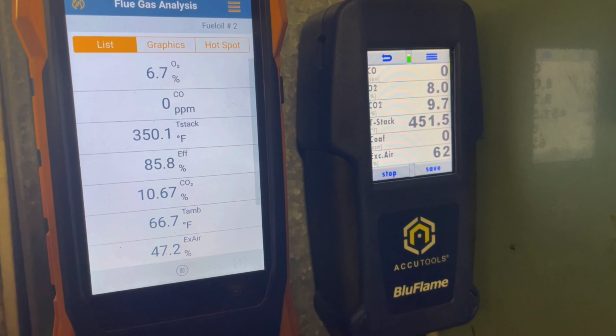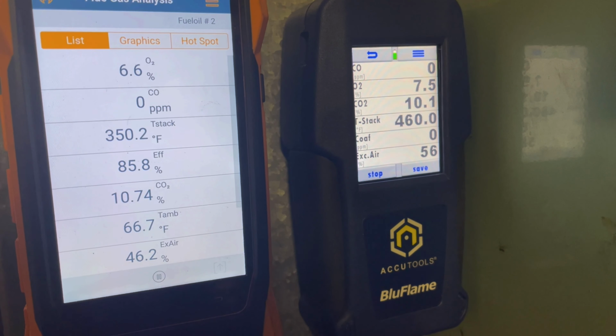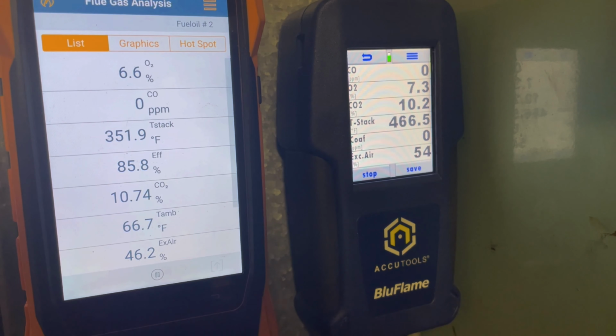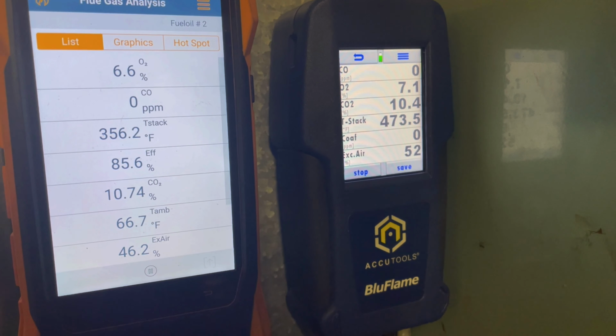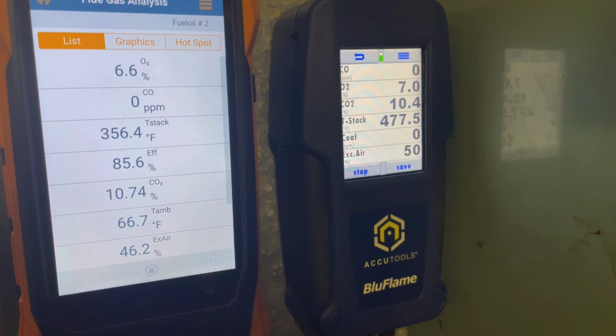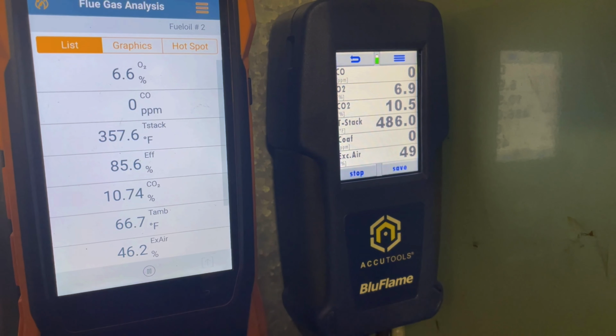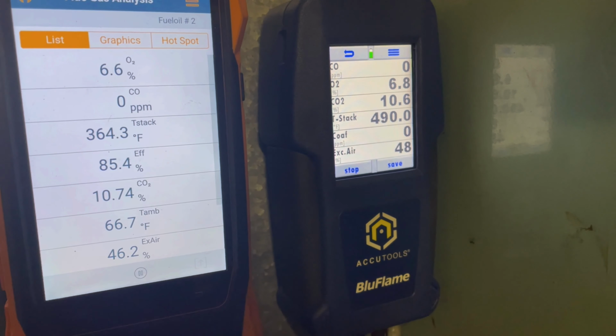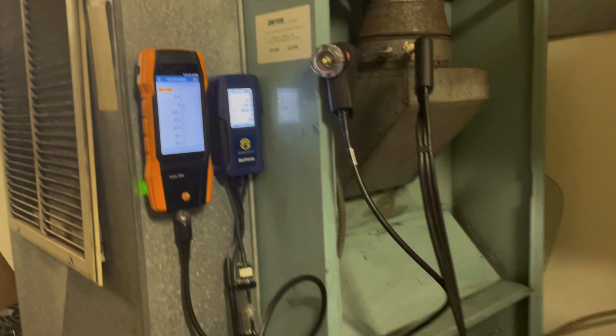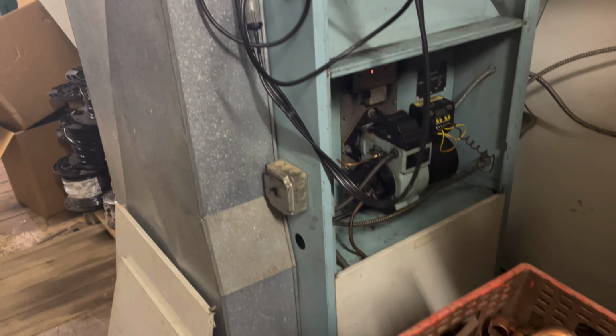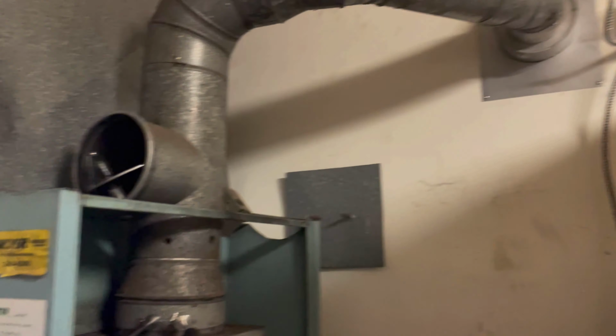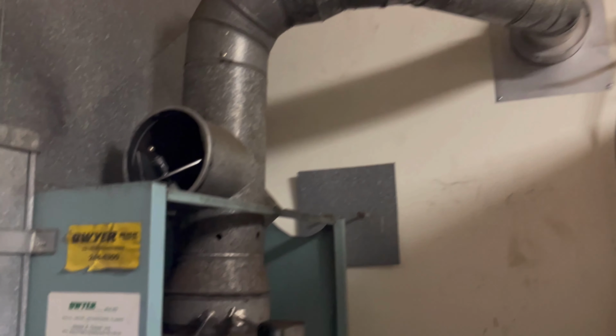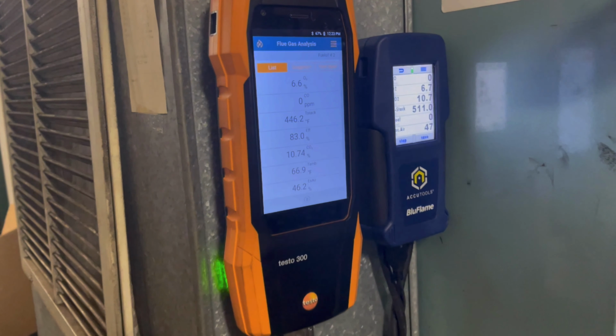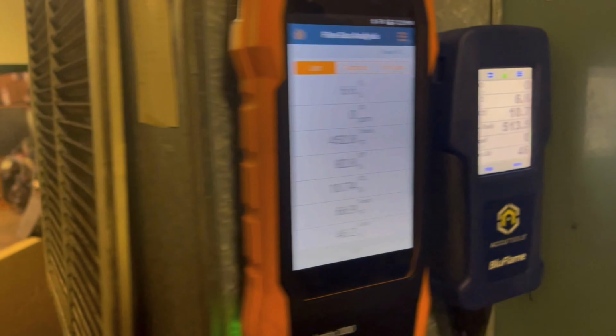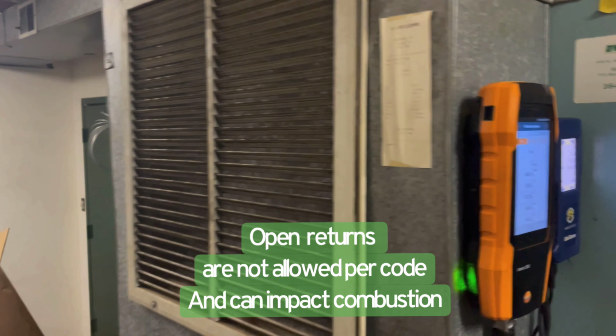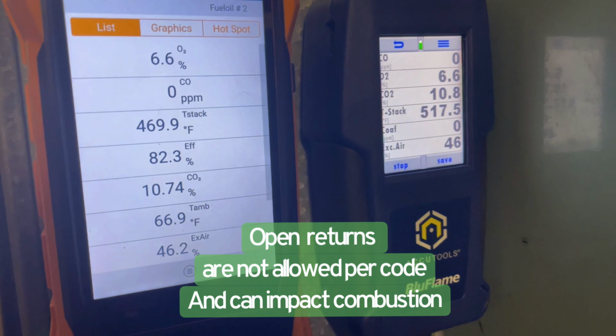With combustion analysis, this tool provides the technician important information such as efficiency, how well the fuel burning appliance is operating at, and of course safety. The information that we look at is oxygen, carbon monoxide, carbon dioxide, excess air, and temperatures. This is an older Williamson warm air furnace, oil fired, that's power vented. It doesn't help that we have an open return.